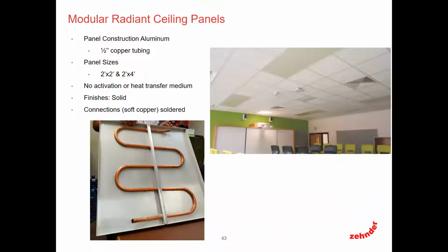Modular panels. Our industry defines a modular panel as really an aluminum pan that's broken up on four sides, as seen on the lower left, and then a copper tube fastened to the back side of it. Typically, they come in 2x2 and 2x4 only. What you'll notice here is that there is no activation, and I'm going to talk a little bit more about activation in a second. But what you're really looking at is the copper tube itself just to the back side of the cassette. There's no activation there. And again, I would only recommend using these for heating only applications. I really wouldn't recommend these for cooling.